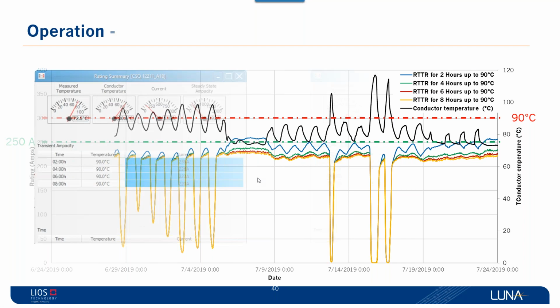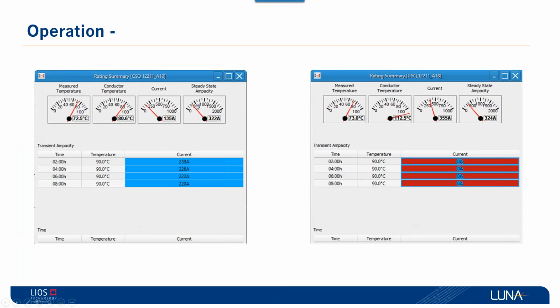What gets very, very interesting as well is that at the end, they have this screen out of the software that they can bring into the dashboard, and see that for the next 2 hours, they can push 239 amps. So if somebody calls them and asks for a bigger load of about 220 amp, they say, yes, I can give you 239 amp for 2 hours, and I can give you 226 amp or 220 amps up to 8 hours. After that, I cannot go any further.